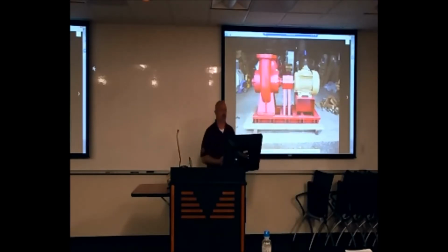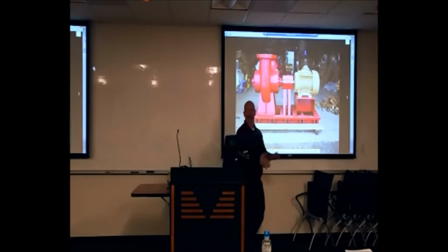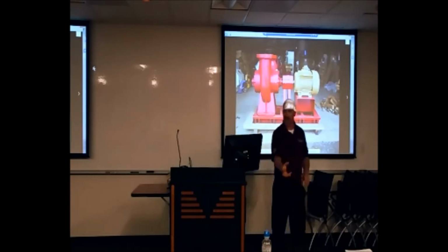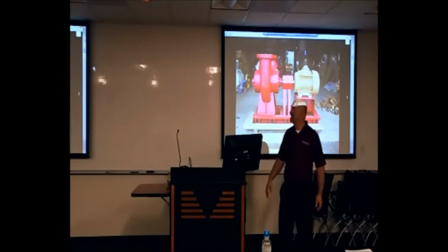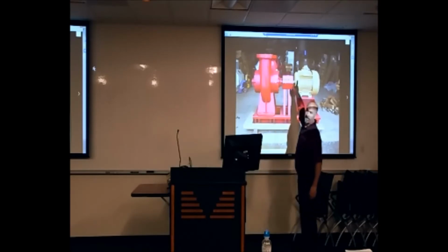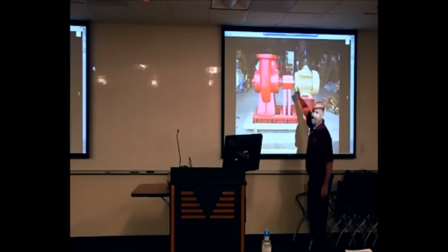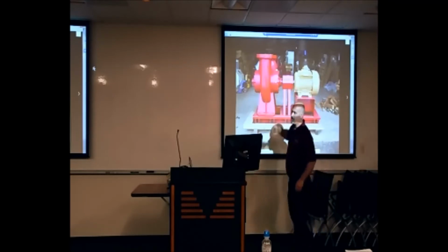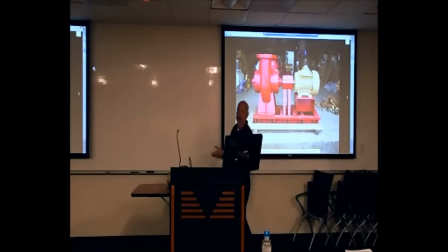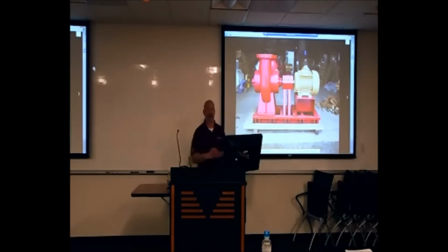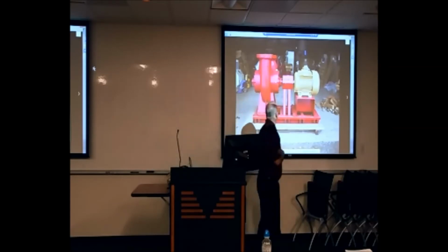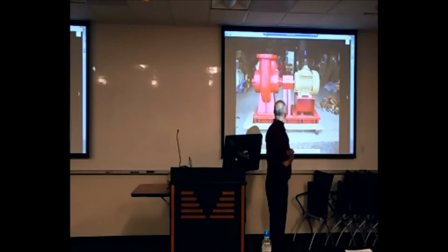I've had a lot of people get the brand new pump motor, see that thing on there and think it's part of shipping, pull it off, throw it on the ground, and install the motor. Less than a month later, the bearing on the motor right here is going out. This one's still fine. So keep those on there whenever you do any service. Don't lose them. That's probably a big culprit I find when somebody's just done service and, oh, we already lost the bearing. It was because the week after it had just rained. So that's probably one of the key things.